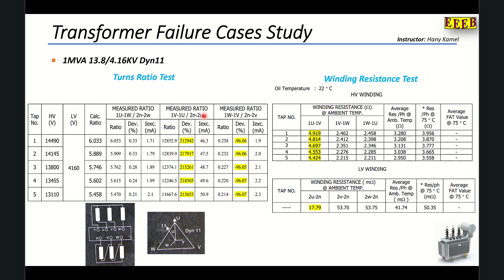Next phase: 1V1U over 2N2U. This is the measured ratio and this is the error. The error is more than 0.5% as we can see, and there is more excitation current as well. This means there is a problem in this phase.